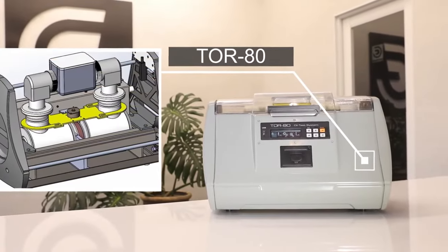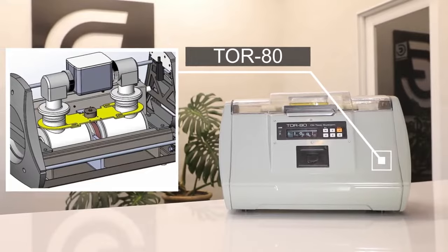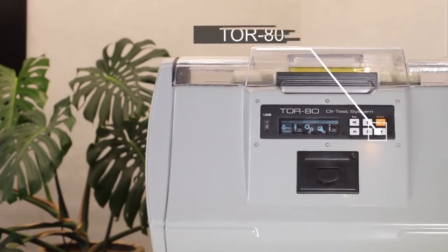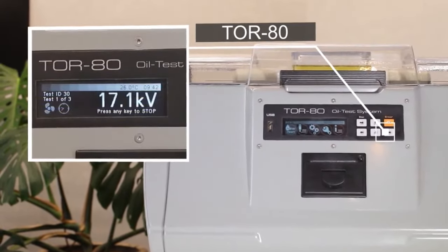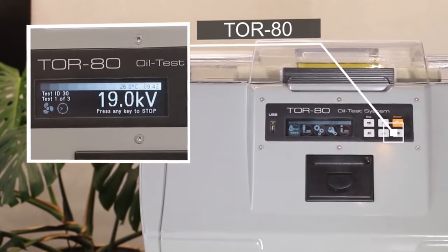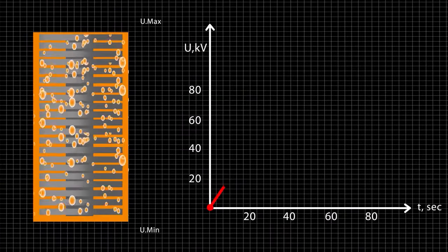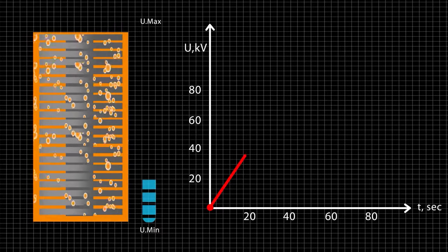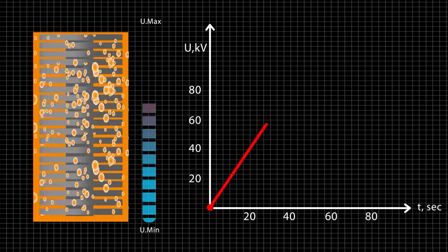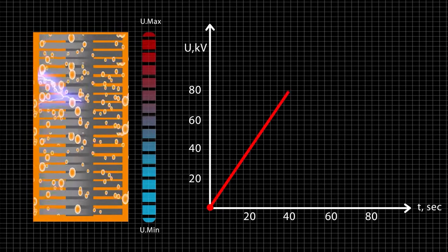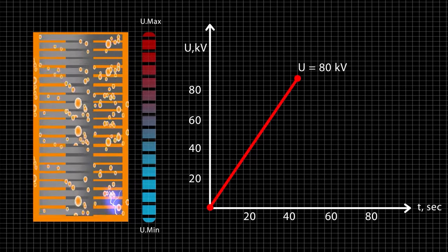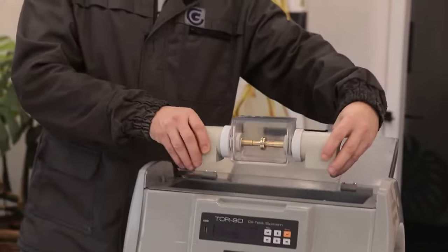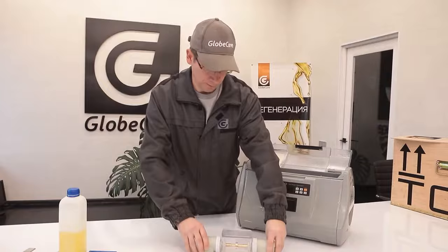Here is the TOR-80 device for measuring the electric breakdown voltage. It operates by gradually rising voltage on the secondary winding of a high voltage transformer from 0 to a maximum value, or to a value at which a dielectric breakdown occurs. The high voltage cutout time after breakdown is less than 4 microseconds. In this, TOR-80 surpasses all similar devices in existence.